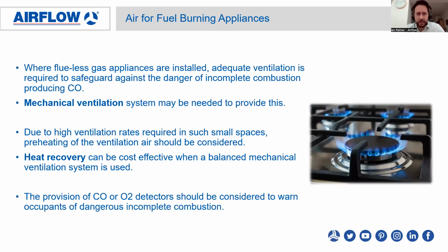Providing air for your fuel burning appliances. So where you've got flueless gas appliances installed, ventilation is required to safeguard against the dangers of incomplete combustion. So a mechanical ventilation system may be needed to provide this. Because of the high ventilation rates that are needed, preheating of the ventilation air should also be considered. So this is where heat recovery comes in as the most cost-effective way of doing this. And you can also add in CO or O2 detectors, which can then be considered to warn the occupants of the dangers of incomplete combustion.